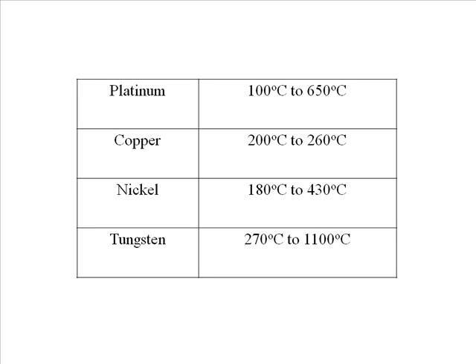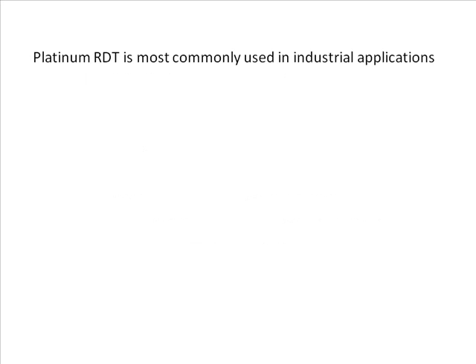And for tungsten it is from minus 270 to 1100 degrees centigrade. Among these metals, although platinum is most expensive, still platinum RTD is most commonly used in industrial applications as other metals mentioned here are not totally free from corrosion and oxidation.